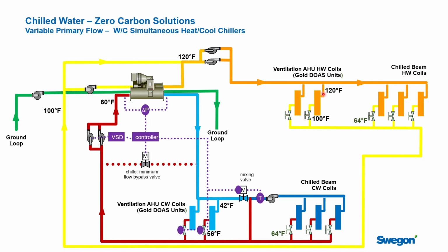Now, in a lot of commercial chilled beam designs, you're going to be in a net heat gain almost all the time, for almost every hour that the building is operating, which simplifies it greatly. And you really do want to say, hey, I'm going to take that heat from the building, wherever it's being generated, and shift it to where I need it in the building, generally moving from the core of the building out to the perimeter.